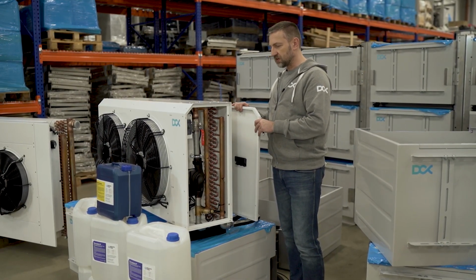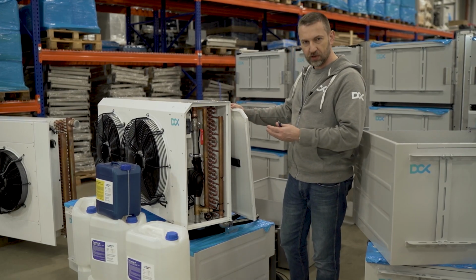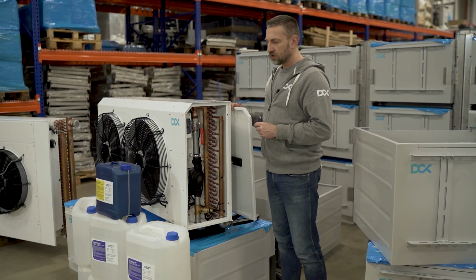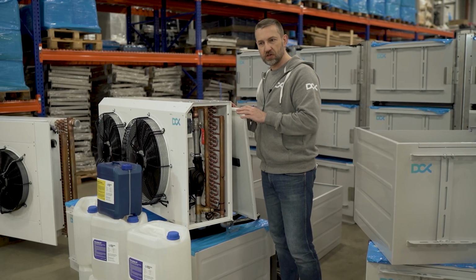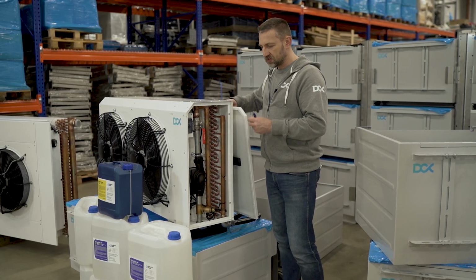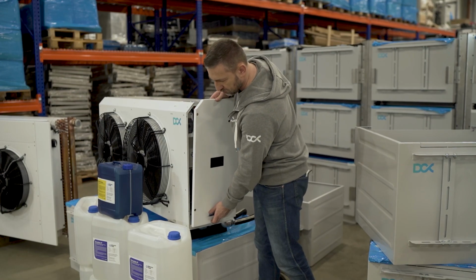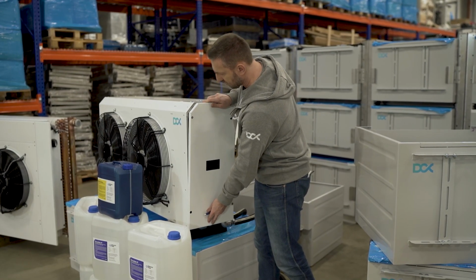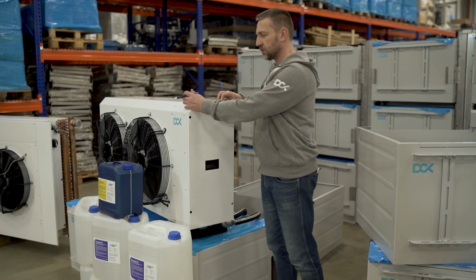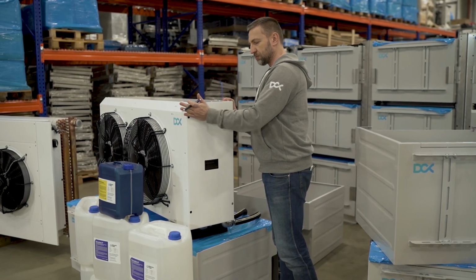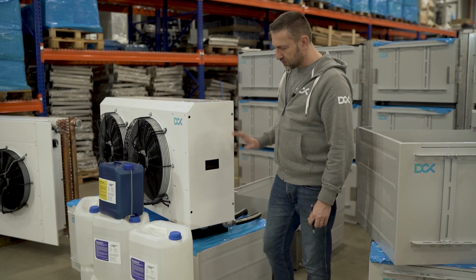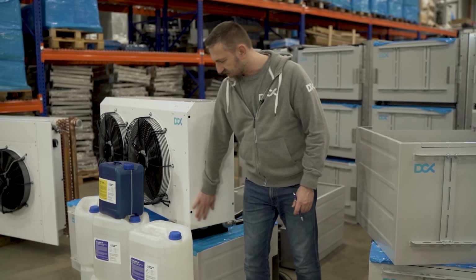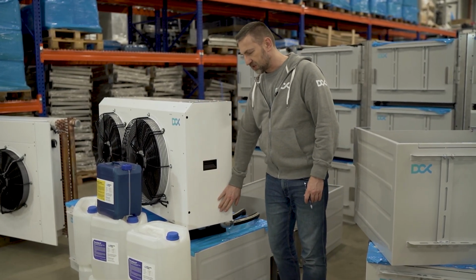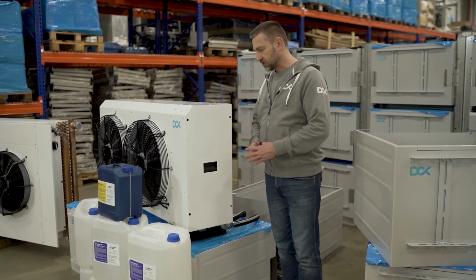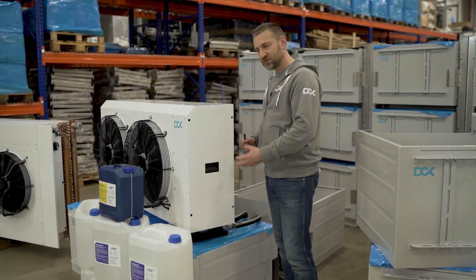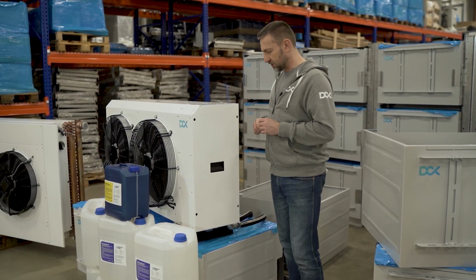That 40 kilowatt capacity is achieved by the 64 square meters of heat rejection area, of heat exchange area, and this is actually enough to cool your overclocked miner configuration during the hot summer days. One thing to remember during the operation after the system is installed: you should make sure that the compartment is fully closed, so we are not sucking the air through the side of the dry cooler, but basically only through the coils.